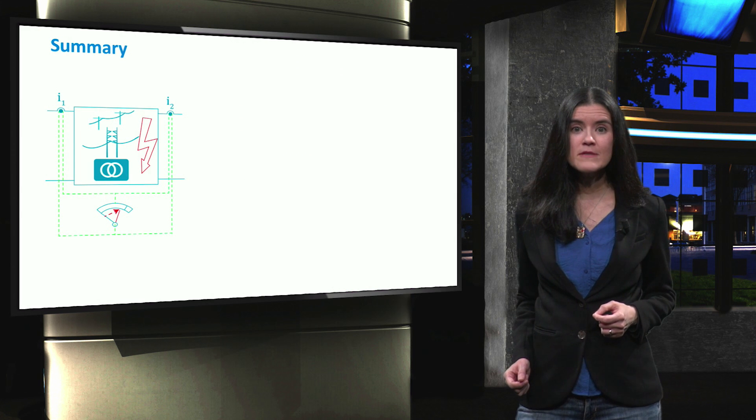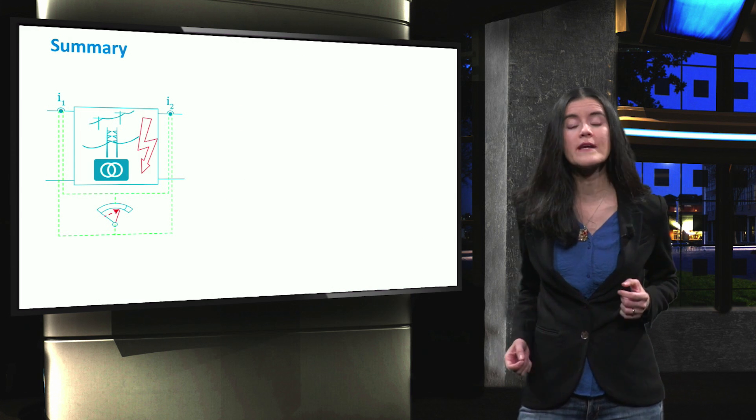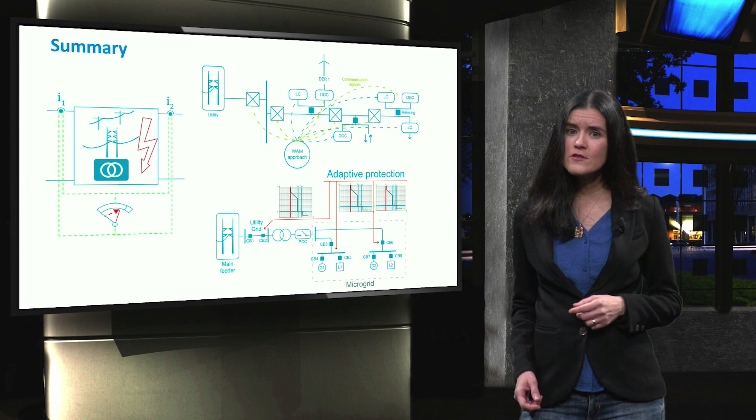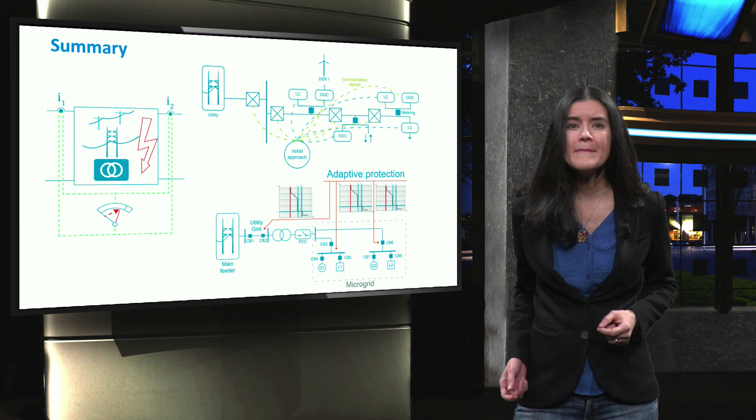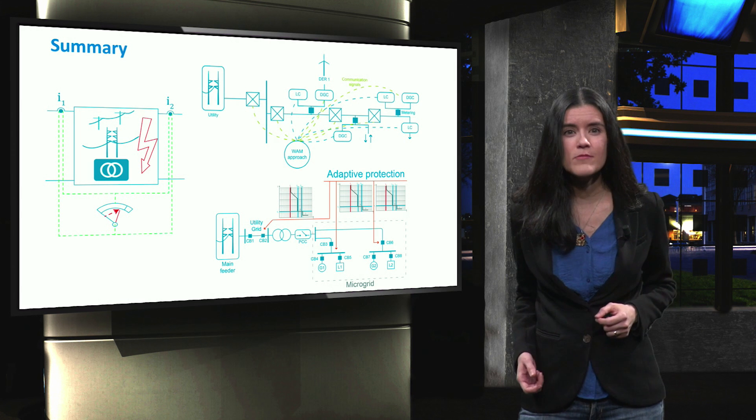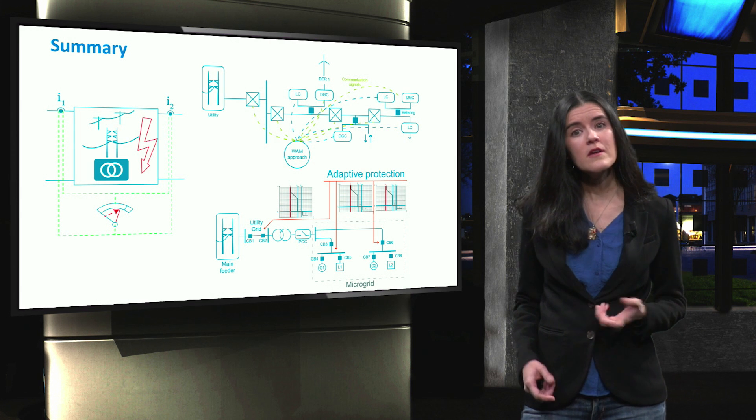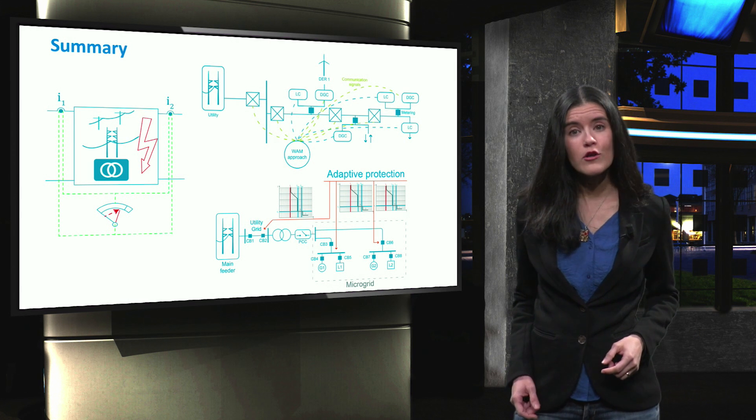Let's now wrap up. We evaluated various protection schemes in microgrids. We saw how communication increases the selectivity of the protection method, such as differential protection, communication-based, and adaptive protection methods. The reliance on the communication network, however, makes the protection system less dependable, needing a backup protection system and increasing the overall cost of the system.